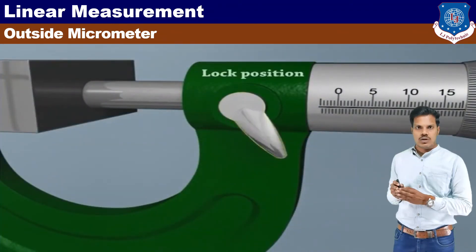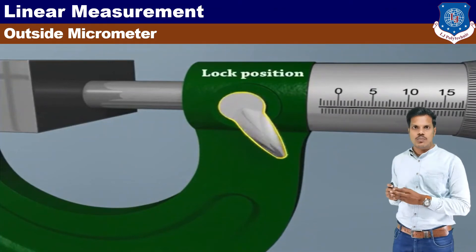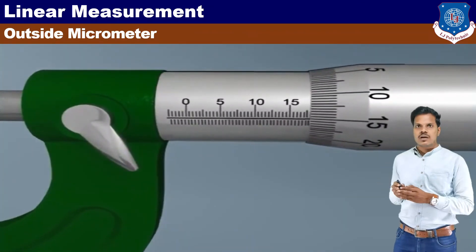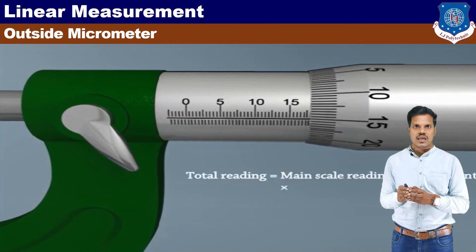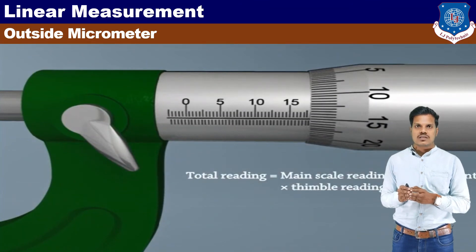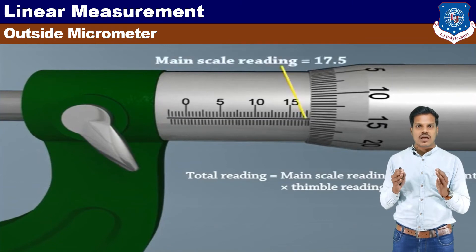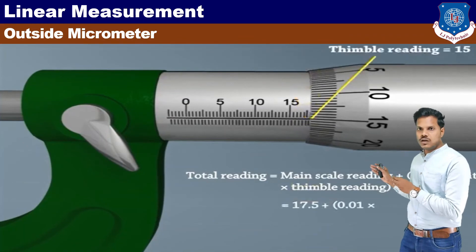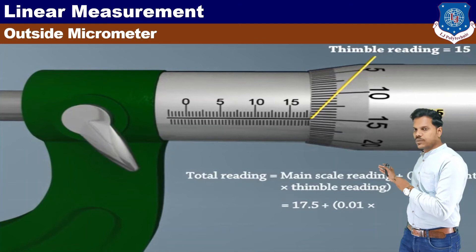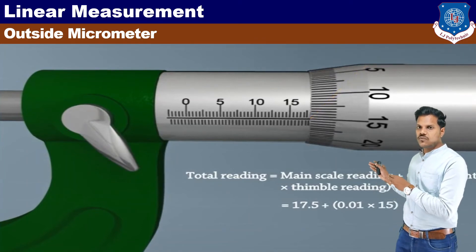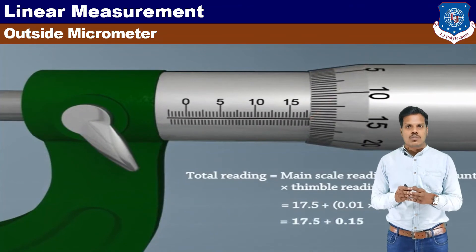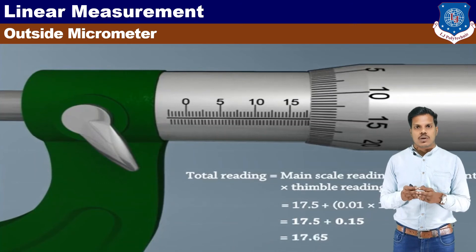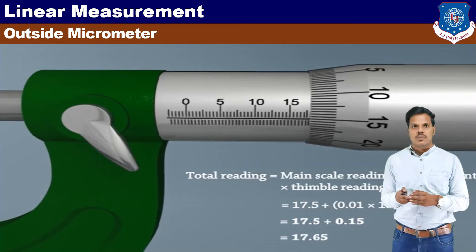This is the ratchet screw application. We lock the screw with the locking screw. Then we calculate the reading: main scale plus least count multiplied by vernier scale reading. The main scale reading is 17.5, plus least count 0.01, multiplied by circular scale reading of 15. So the total is 17.5 plus 0.15, that is equal to 17.65 mm. This is the calculation for the outside micrometer.